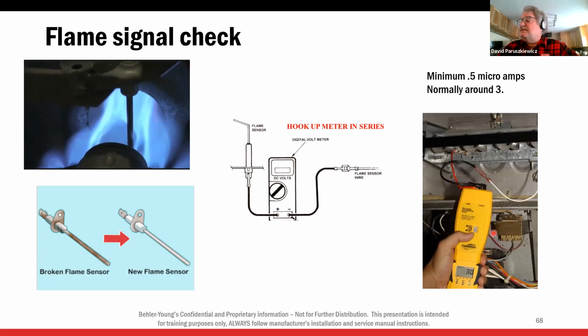So just about everybody's meter does this nowadays. We used to have special meters. So we're going to unplug the wire from the flame sensor, plug it into one side of your meter, plug the other side of the meter into the flame sensing wire, fire the furnace up or the unit up. At 0.5, it will drop out. So if I do not have a 0.5 flame signal, then that's why it's locking out. If it's higher than 0.5, then it shouldn't be locking out.